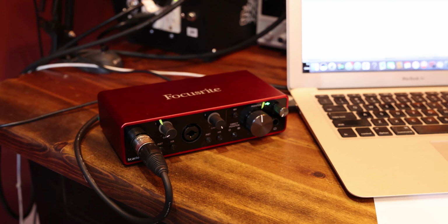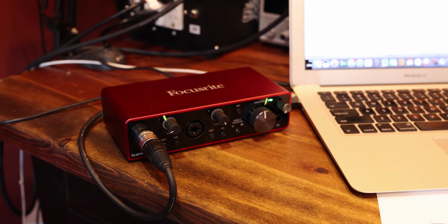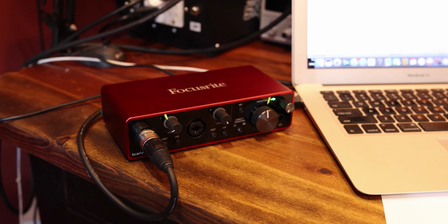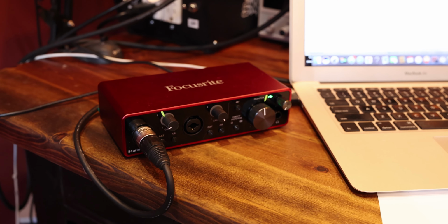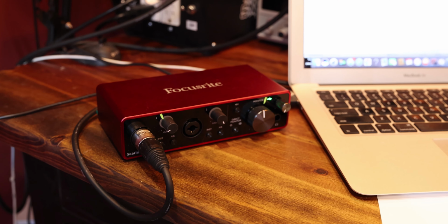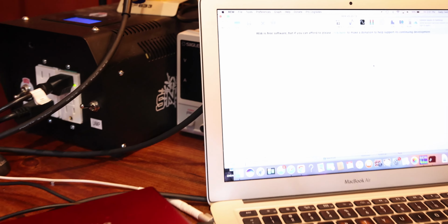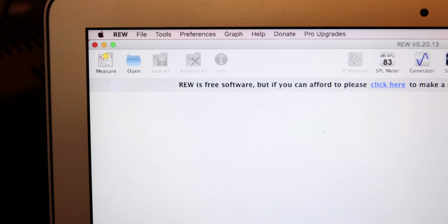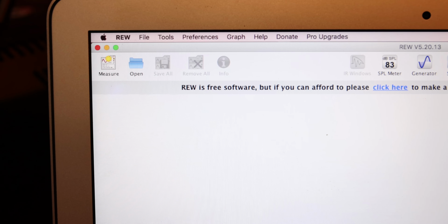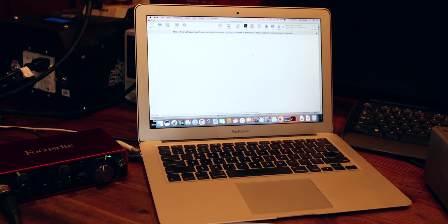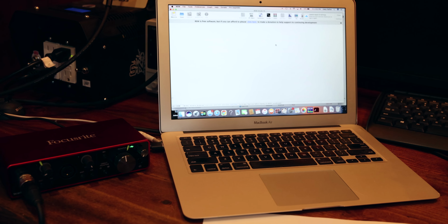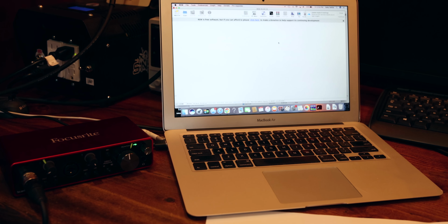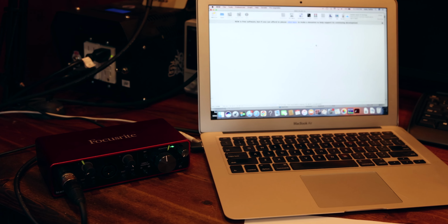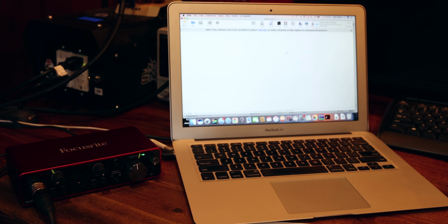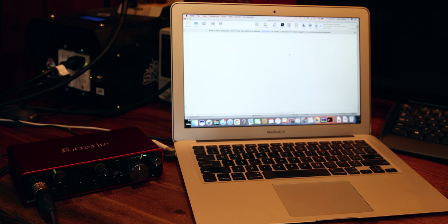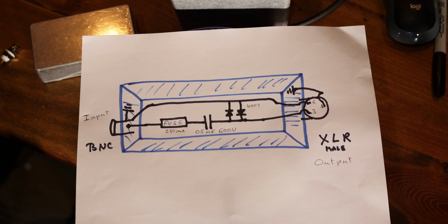So to measure anything at the microvolt level, we need to amplify that level. So we're going to use a sound card, and that's going to amplify that ripple, because ripple is just like music. It's basically an AC signal. And then we're going to use the computer with software that's free, and it's called REW. And you're going to need a laptop that can run on battery. So this way you can avoid any noise. And also the sound card is going to be connected to that laptop, and that's also going to run on its own batteries, and then it will also be very low noise.